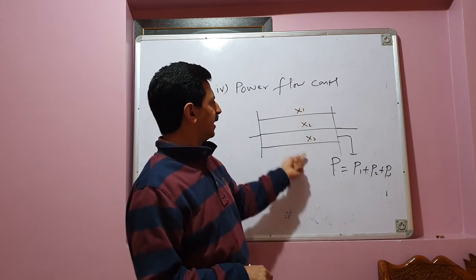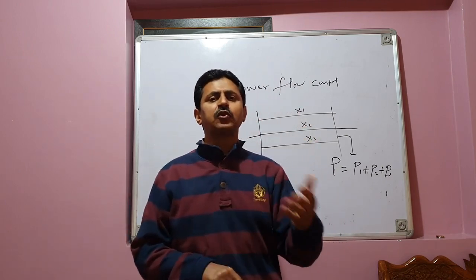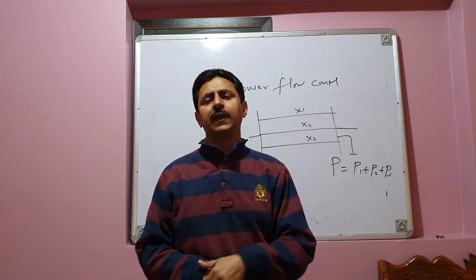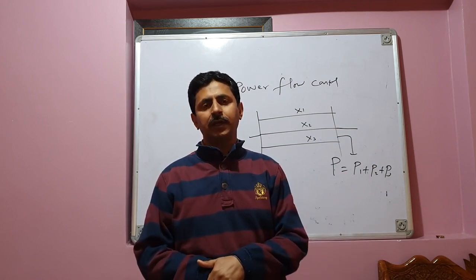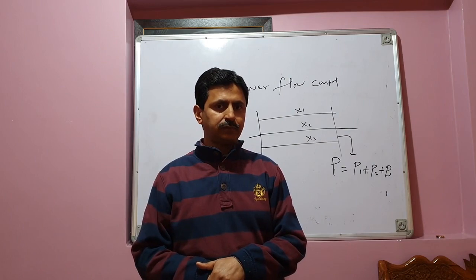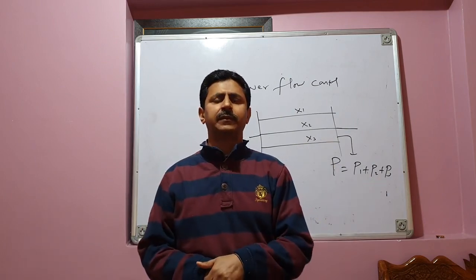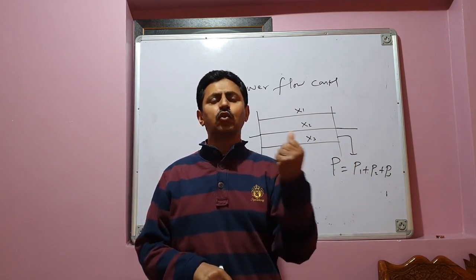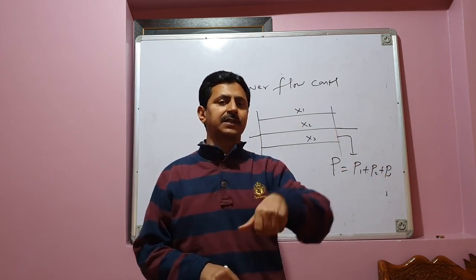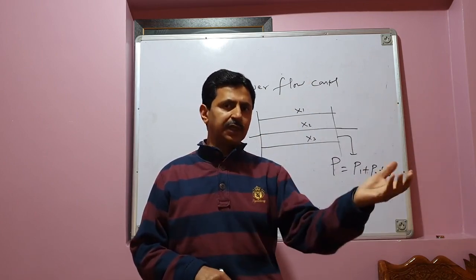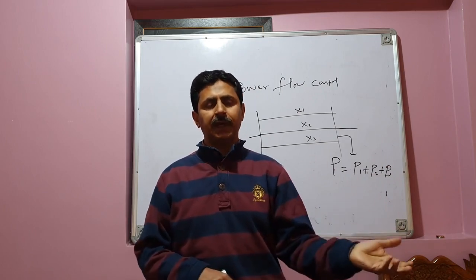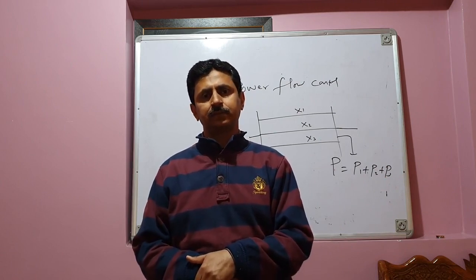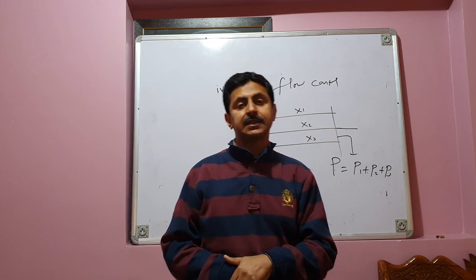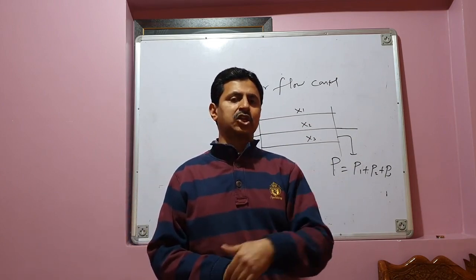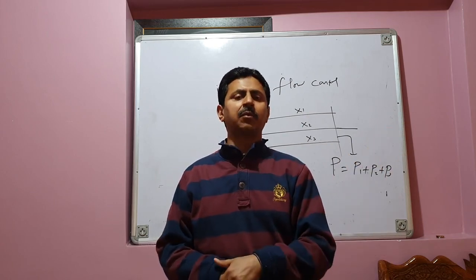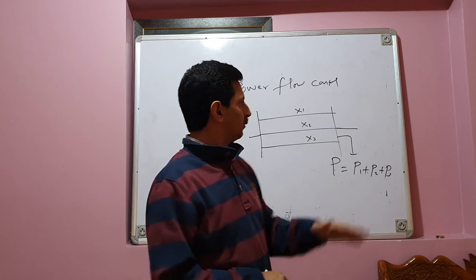And the other line, say line number 3, has a reactance of X3. Suppose it has the smallest reactance among the three lines. So it will carry the maximum share of the power, and it may get overloaded in that case. Suppose it also has a capacity of transmitting 100 megawatts, but its reactance is so small that instead of transmitting 100 megawatts, it is transmitting, say, 150 megawatts. So it gets overloaded and creates problems. The line may trip, and it will cause a large scale disturbance in the system. So the power flowing over the lines is decided by the impedances of the lines, and some of the lines may be underutilized and some may get overloaded. Therefore, we want control over the flow of power.